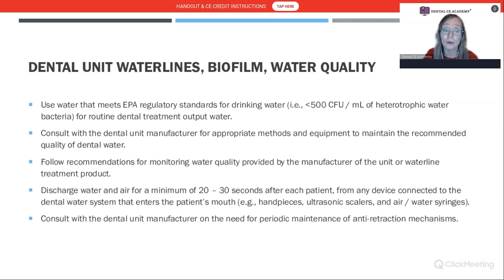And so biofilm will grow inside these water lines. The water lines are small in diameter. The flow is slow, and the tubing is just conducive to biofilm growth. Right? You should be using anything that meets EPA regulatory standards for drinking water. So less than 500 colony forming units of heterotrophic bacteria. That will be okay for routine dental treatment if you're using tap water, but again, you still have to test these lines. The same for bottled water.